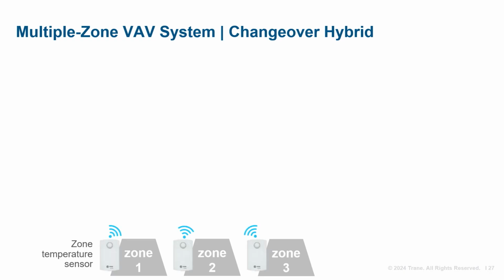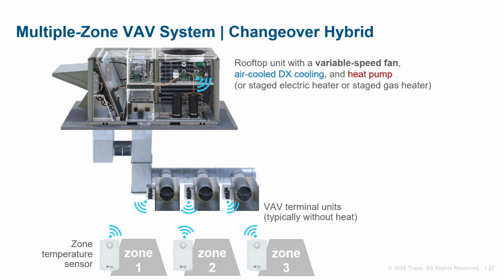Next, Eric will review multiple zone systems, meaning the building has multiple thermal zones served by a single rooftop unit. This system uses VAV terminal units and a rooftop unit or split system. Each thermal zone is equipped with a communicating zone temperature sensor and VAV terminal unit. The temperature sensor in each zone is used to determine how much cooling or heating is needed, and then the VAV terminal modulates the flow of cool or warm air to maintain zone temperature at set point. To provide conditioned air to the VAV boxes, we have a packaged DX rooftop unit.